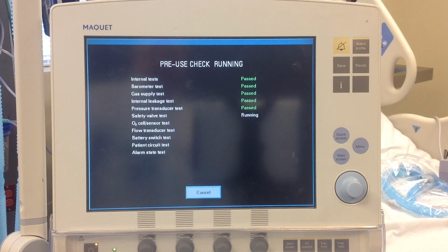If you go from a non-heated to a heated wire, redo the test. If you go from an adult to a neonatal circuit, redo that test. The test is really, really quick. Takes maybe 30 seconds, and while you're doing that, the patient can be bagged. As you can see, once we hook this up, this pre-use check is completely automated.